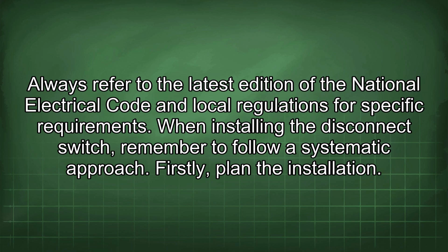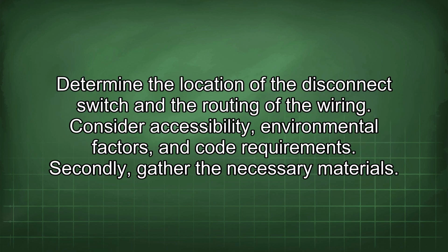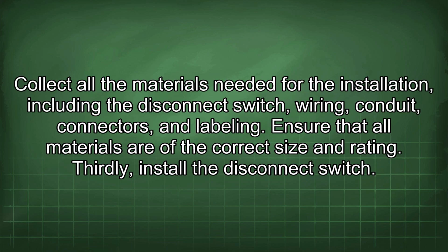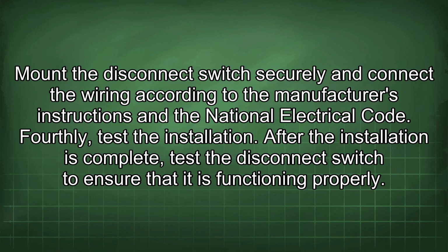When installing the disconnect switch, remember to follow a systematic approach. Firstly, plan the installation. Determine the location of the disconnect switch and the routing of the wiring. Consider accessibility, environmental factors, and code requirements. Secondly, gather the necessary materials. Collect all the materials needed for the installation, including the disconnect switch, wiring, conduit connectors, and labeling. Ensure that all materials are of the correct size and rating. Thirdly, install the disconnect switch. Mount the disconnect switch securely and connect the wiring according to the manufacturer's instructions and the National Electrical Code.